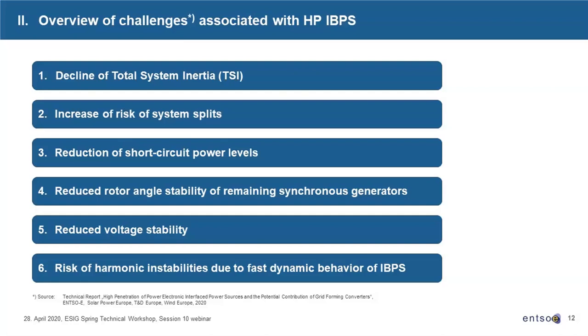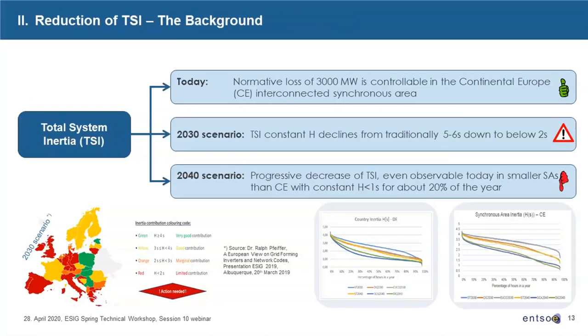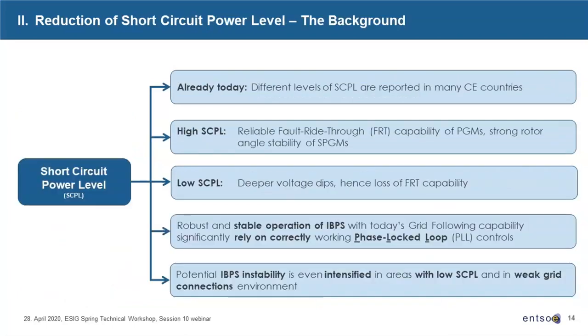We experience a reduction of short circuit power levels, reduced rotor angle stability, reduced voltage stability, and the risk of harmonic instabilities due to the fast dynamic behavior. All of these six aspects you can elaborate on in more detail. For example, this is just a summary of something which I reported more extensively last year in my presentation in Albuquerque about the decline of the system inertia in the 2030 and 2040 system development scenarios of ENTSO-E, where we see that it is a significant risk and a number of member states need to be alerted about this and need to prepare countermeasures to be able to mitigate events and incidents which are related to low inertia.